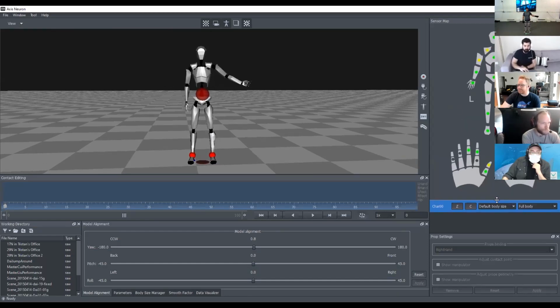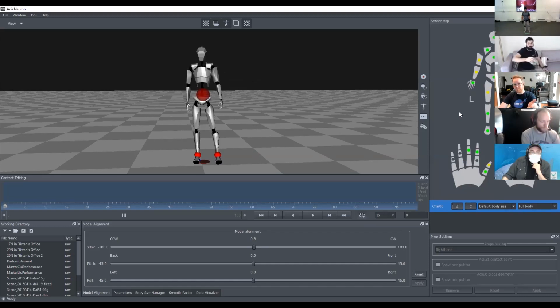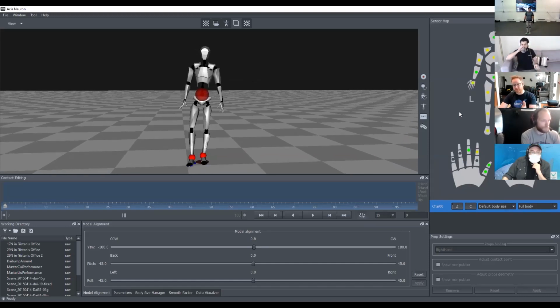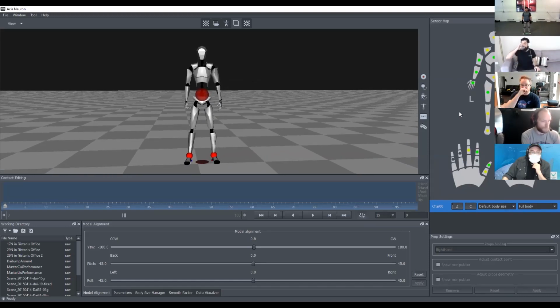This tells you what's connected, what's functioning, what's not. Here you can see everything's green and yellow, which is perfectly fine for signal strength. Sometimes your sensors could dip into the red, and it's not that big of a deal as long as it's only for a couple of seconds. If a sensor goes red for a very long time, or if multiple sensors go red for a long time, that's an issue that you need to start troubleshooting. A key indicator is whether the sensor is magnetized. If it is red for a long time, that's normally an indicator the sensor is magnetized, so you'd want to perform the demag procedure on that.